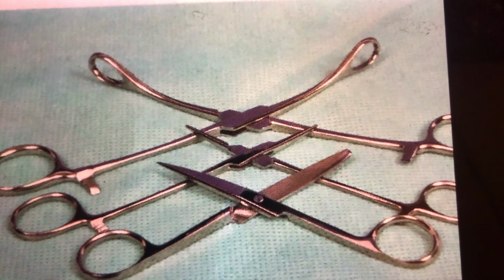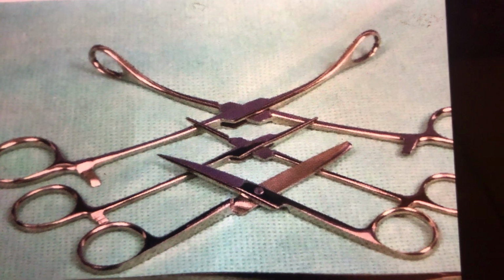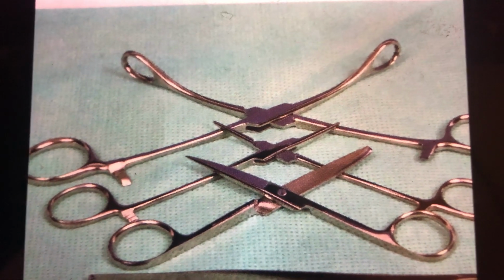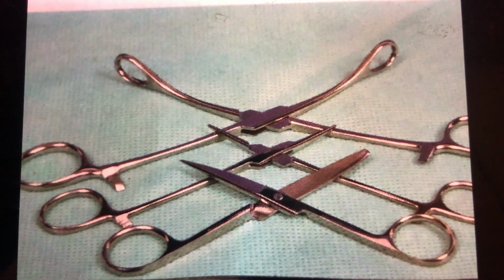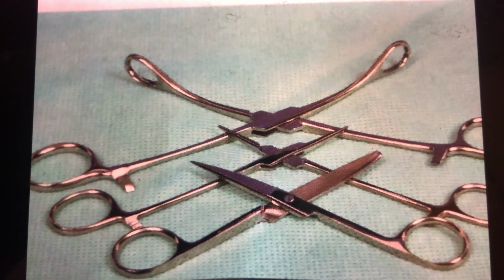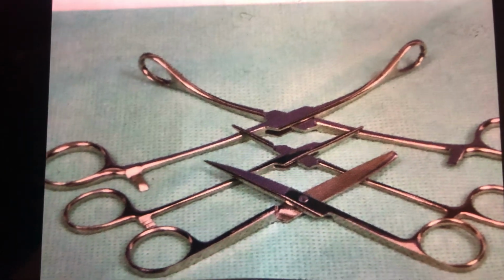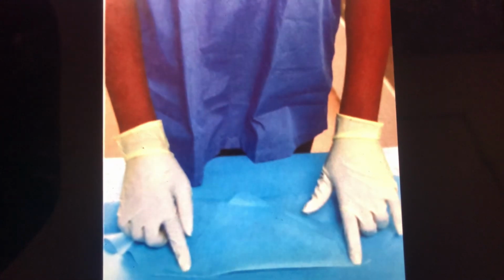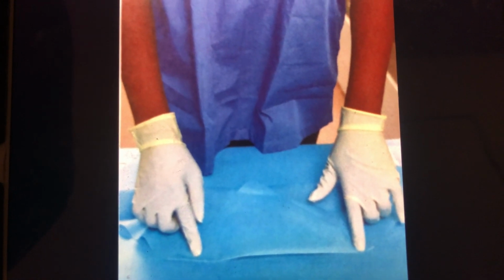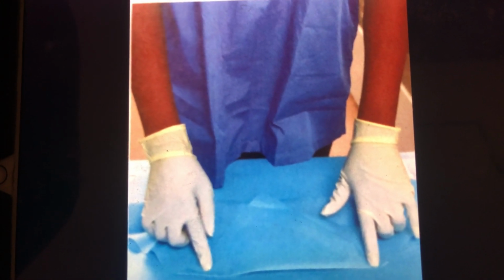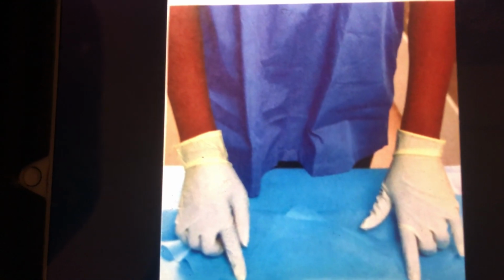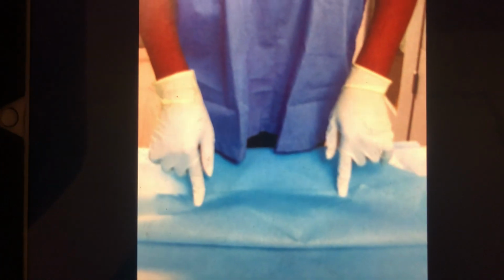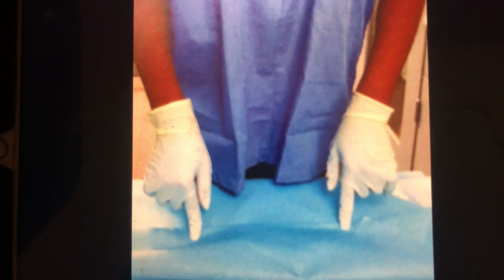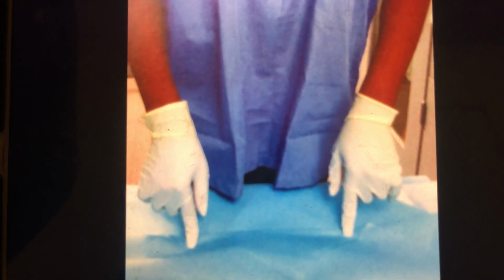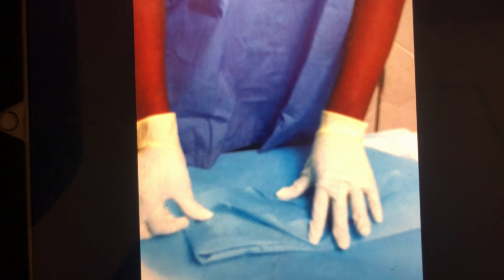Its teeth or tip should be shielded with cotton or gauze. Depending on the clinic policy, a biological sterilization indicator or sterilization strip should be placed in the center of the pack to check for sterilization standards. Bring up the bottom corner of the wrap and fold back a portion of it. Repeat the previous steps with each corner, making sure to turn back a portion each time. Fold the last flap over.